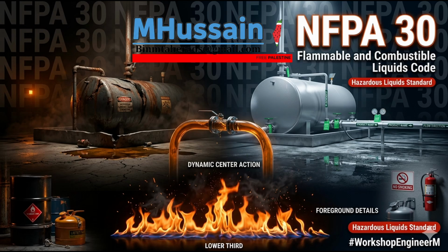Principle number 2, obsess over your container combinations. We spent a lot of time analyzing Chapter 16 and Annex E because the suppression math is unforgiving. You cannot just implement a generic warehouse sprinkler grid and assume you are protected. Right, the protection criteria are inextricably linked to the specific vessel holding the liquid. Are they in rigid, non-metallic containers? Composite IBCs? Sealed steel drums? Are they explicitly designated as relieving or non-relieving?